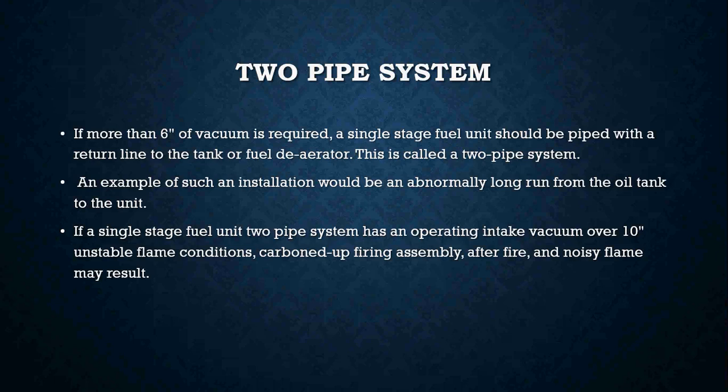On two pipe systems, more than 6" of vacuum is required. A single stage fuel unit should be piped with a return line to the tank or a fuel deaerator — these are called two pipe systems. An example would be an abnormally long run from the oil tank to the unit. If a single stage fuel unit on a two pipe system has an operating intake vacuum over 10 inches, you can have unstable flame conditions, carbon buildup on firing assemblies, after fire, and a noisy flame.